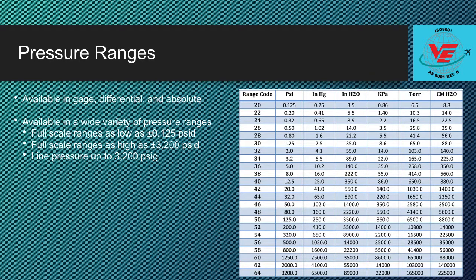They may be marked with a Z for zero and an S for span. The P895 is available in a wide variety of pressure ranges and can be configured for absolute, differential, or gauge and vacuum measurements. The P895 can be ordered with a full scale as low as 0 to plus or minus 0.125 psi. With standard accuracy of 0.1% full scale or better, the P895 is one of the most accurate pressure sensors Validyne offers. The P895 is also available in pressure ranges as high as 3,200 psi. These are used to measure typical hydraulic pressures.